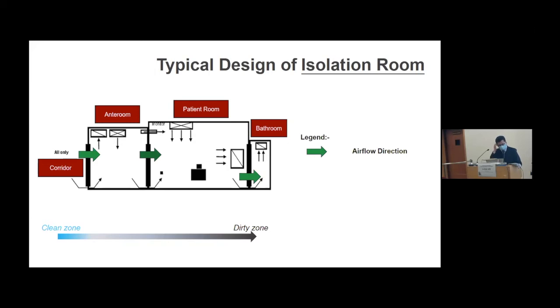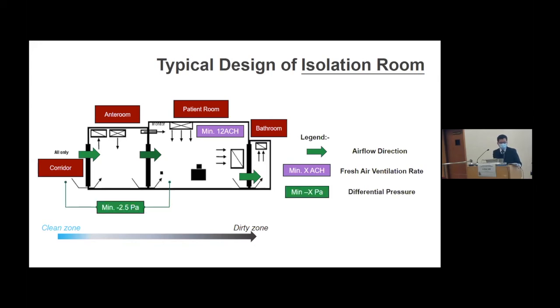In the ASHRAE standards, the design of the isolation rooms should be able to achieve the following requirements. They should have at least 12 fresh air ACH. The pressure differential between the corridor and the isolation room should be at least negative 2.5 Pascal. The standards also require a filtering efficiency of MERV 14 rating or above. And for most isolation wards in public hospitals in Hong Kong, HEPA filters of grade 13, which has a higher filtering efficiency than the MERV 14 rating, are used at the exhaust.